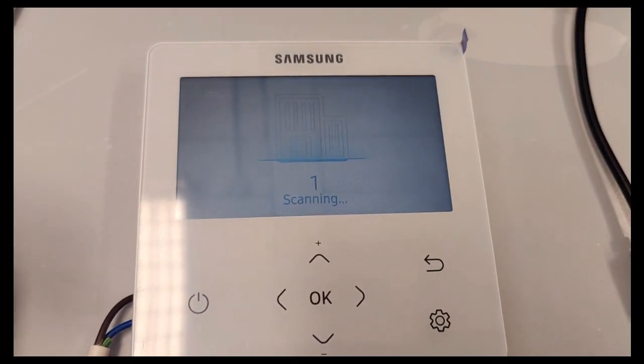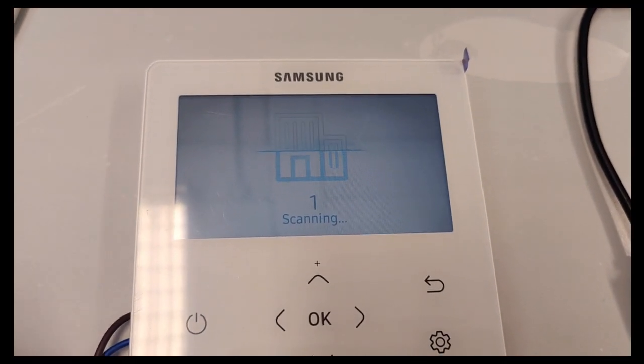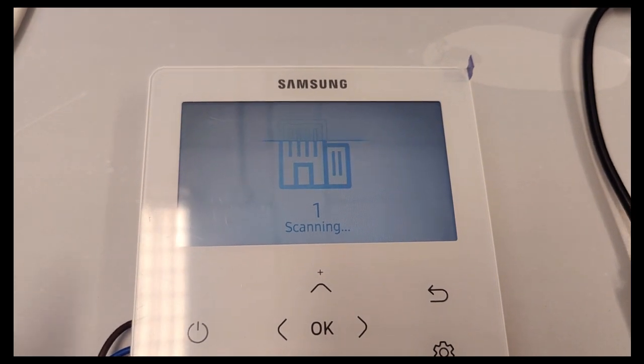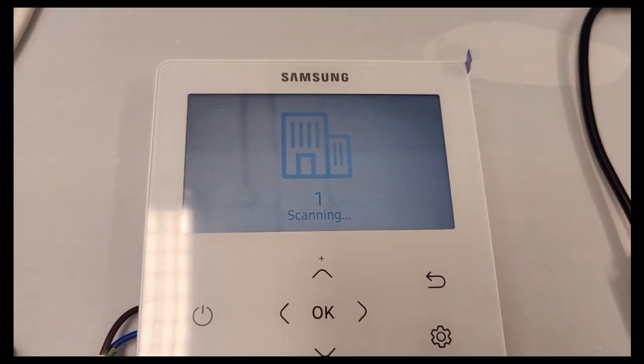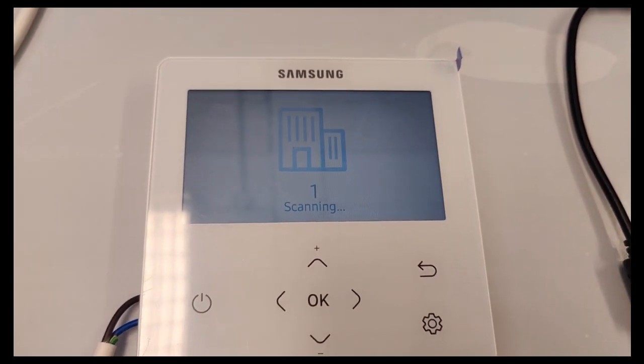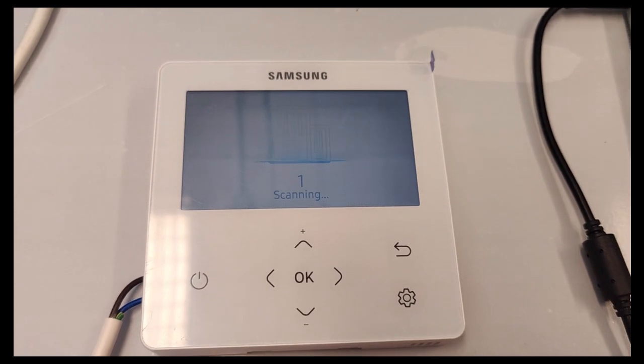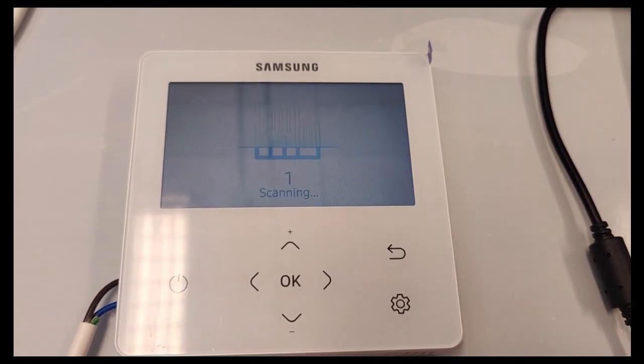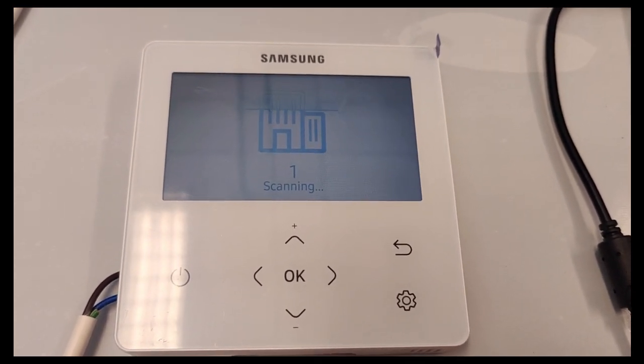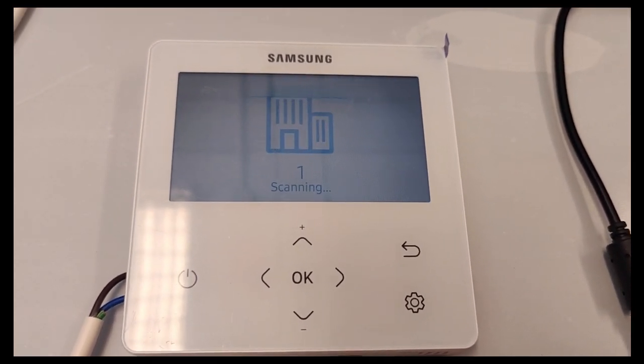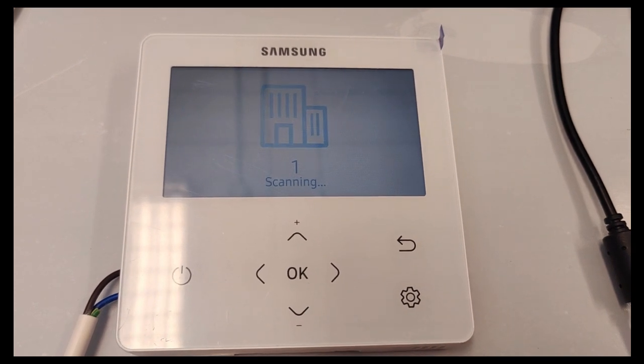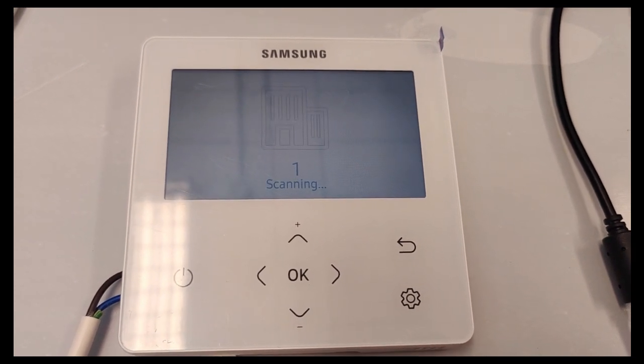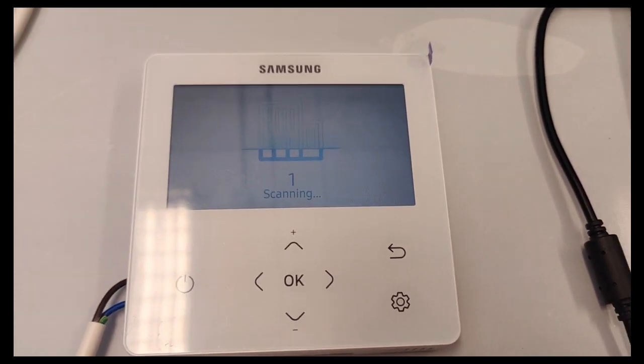If it sticks on scanning zero, you haven't put your comms cable in between the indoor and outdoor, or the power's off to the outdoor. If it says scanning one, things are looking really good. This takes something like 30 seconds. It's just checking out everything's there, checking addresses, doing a kind of handshake, making sure everything's good.